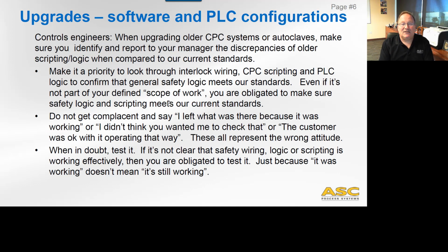Upgrades, software and PLC configurations. So, you know, for your control engineers, when upgrading older CPC systems or autoclaves, make sure you identify and report to your manager any discrepancies of the old scripting or logic as it compares to our new current standards. So you're going to be required to make it a priority to look through that, whether it's wiring or it's scripting or it's PLC logic, to confirm that the general safety logic meets our current standards, okay?